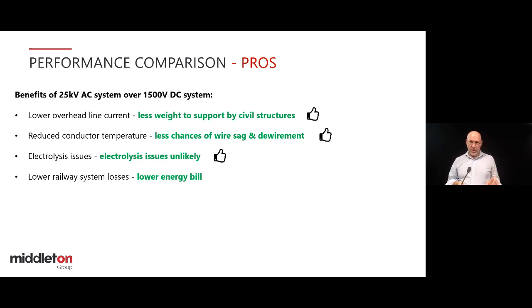If that was run at 25 kV versus 1500, the energy savings would be roughly enough to run 30 domestic dwellings for 1 year. That's just the difference in the traction power systems, nothing else. No train timetables, 30 dwellings for 1 year. So it's a significant amount of energy that you can reduce. So that's another plus. And as I mentioned, fewer substations and transformation points means lower cost as far as the supply side goes. It also means there's a lot less land use.